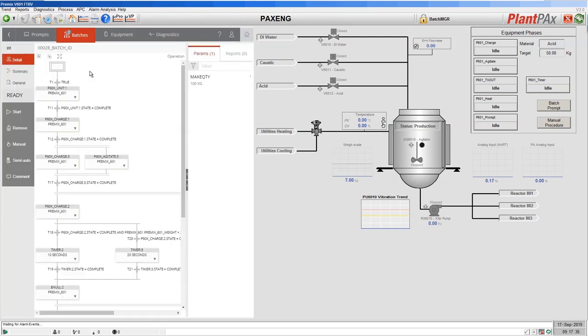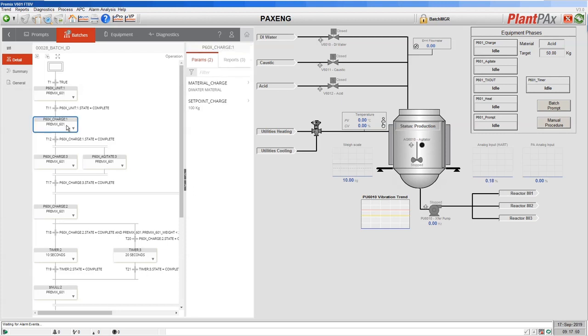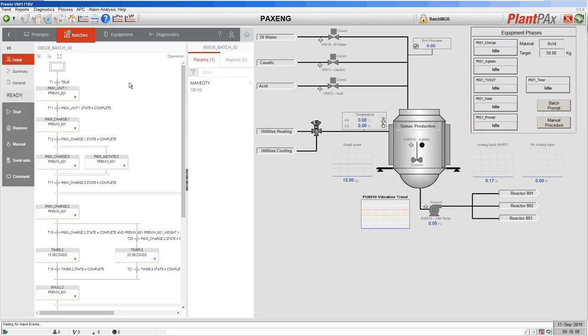Let's select our first batch. Here we can now see the details of that recipe in a sequential flowchart view, so we can see each of those process steps — the equipment phases. If we click on a step we can see the details in the recipe for that step. Here we're running the charge equipment phase; we can see that we have DI water selected and we're going to charge 100 kilograms. From this view we can start the recipe, switch it into manual mode, semi-automatic mode where the batch system will not move on until we allow it, or put it into total manual control and step back into a previous step.